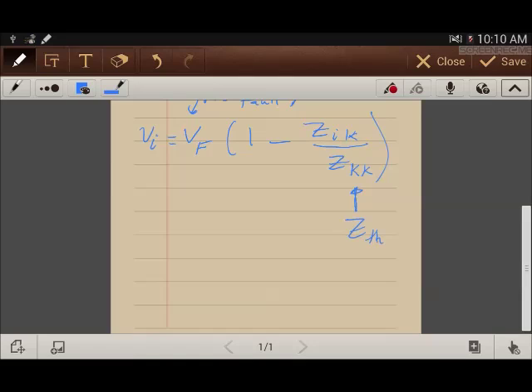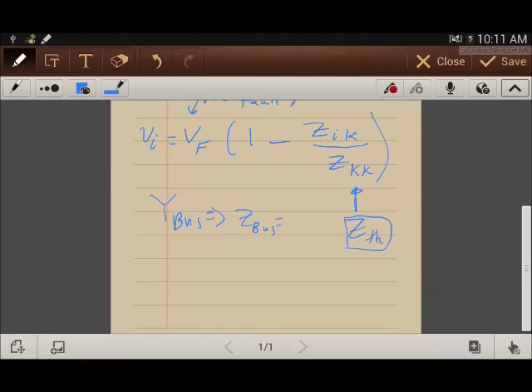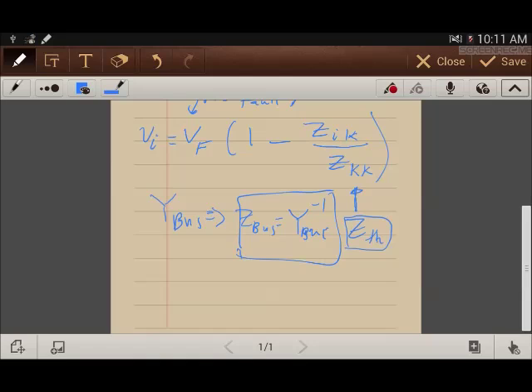Z_kk is the Thevenin equivalent impedance at the faulted bus. I will solve many examples for finding these impedances, the fault voltage, and the voltage at all buses of the system. There are two ways of solving this: either by using the Thevenin impedance or by finding the Y-bus and then finding Z-bus, which will be Y-bus inverse.